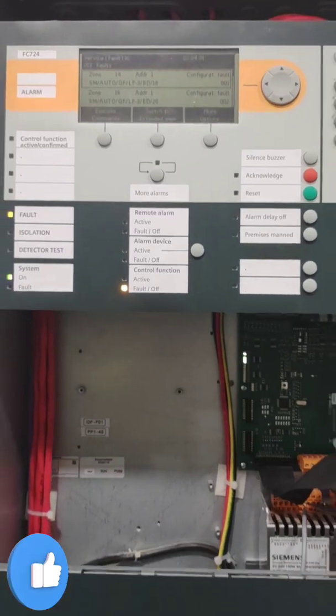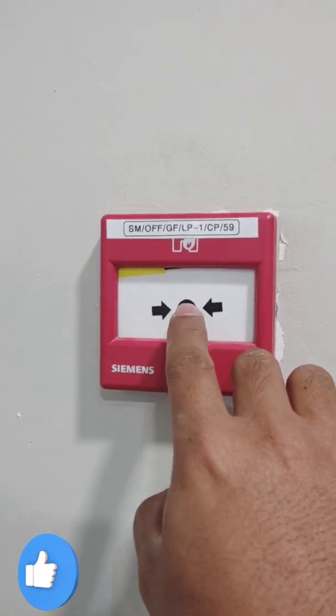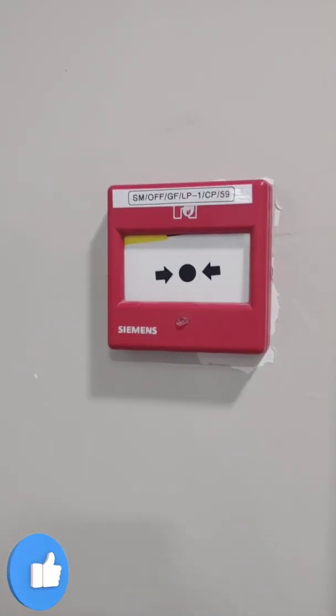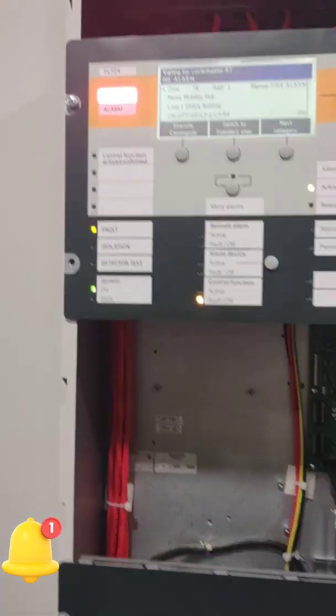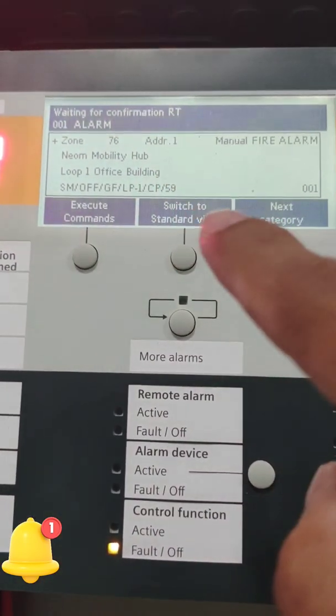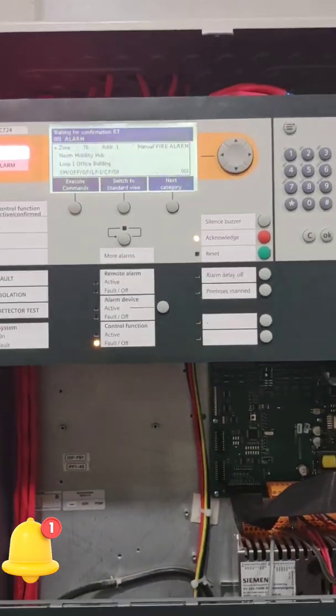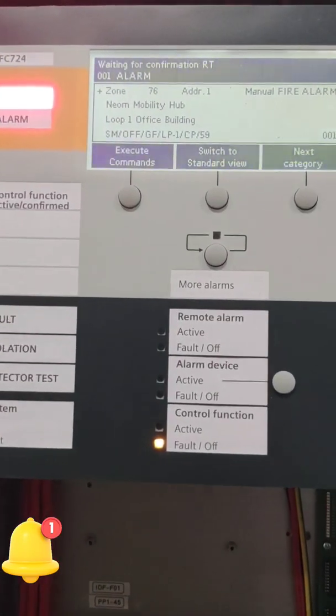So now we are going to test another loop. This is for loop one. We are going to test the call station — manual call point. As you can see, the manual call point is already blinking, and now on the panel you can see the address, the device name, and the location of the call point that we have triggered.